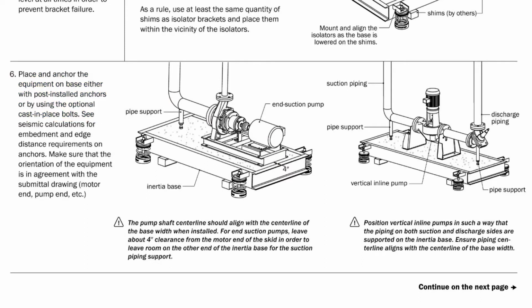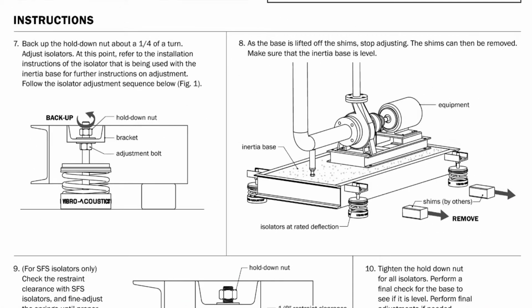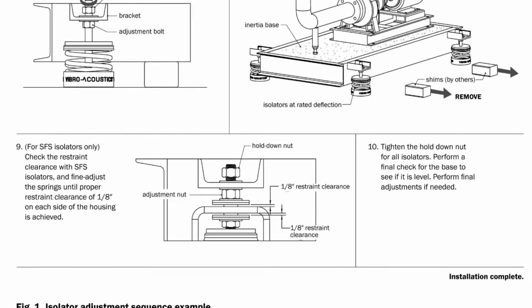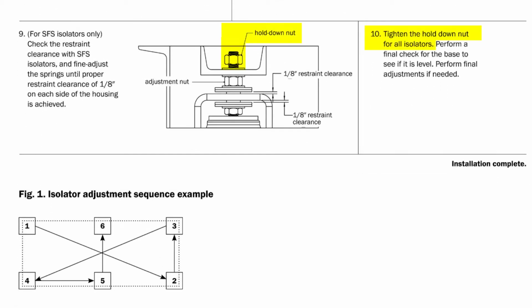The same application requirements apply to any kind of pump. Here we see a base-mounted end suction pump and a vertical inline pump on pump stands. It is best that any elbows also be supported by an inertia base if it has been adequately designed and sized for those. This step shows the isolators being adjusted so that the shims can be removed and the inertia base leveled. We'll check the installation at the job site to make sure the isolators have been adjusted, the shims have been removed, and the base is reasonably level. We'll look at installation instructions for the isolators in a moment. Finally, all of the hold-down nuts should be tightened on all of the isolators.